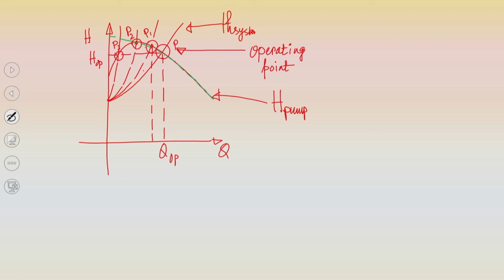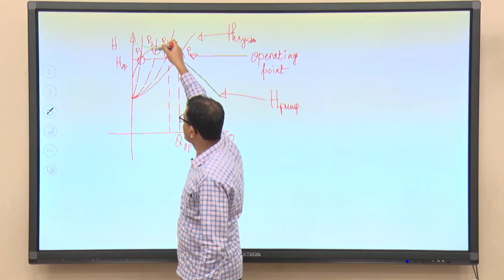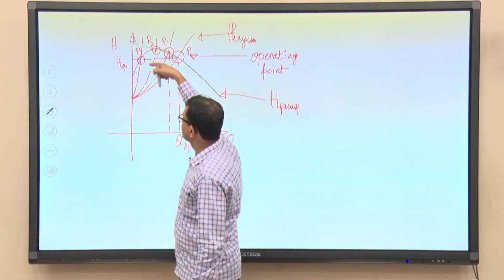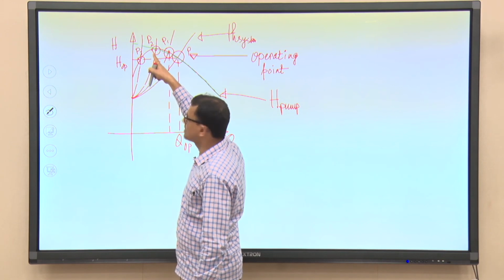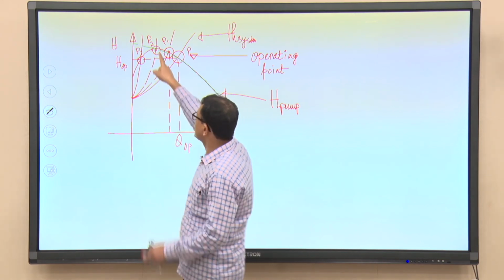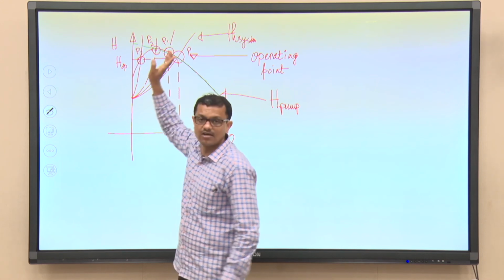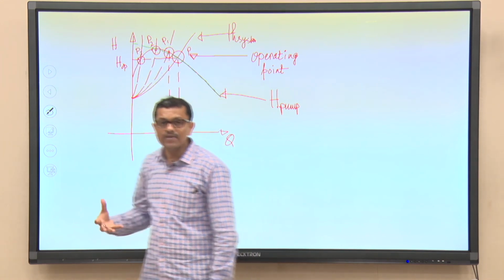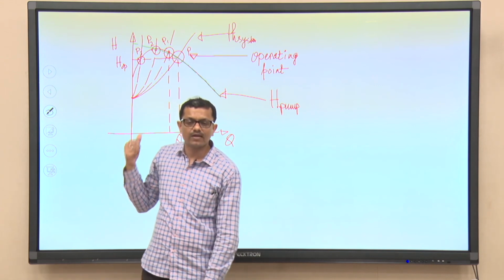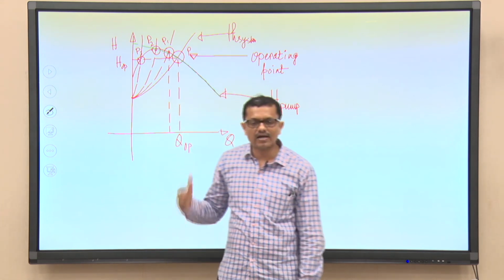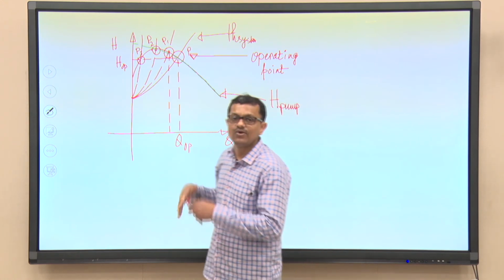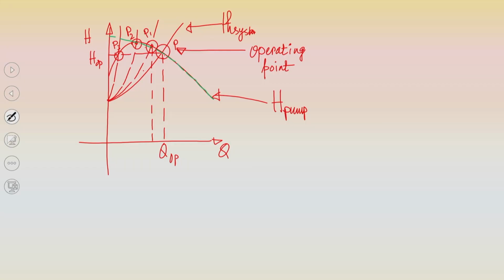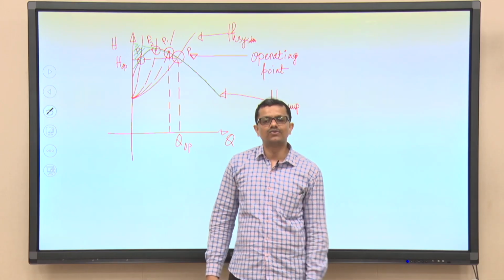Because even though the operator has closed the valve and the operating point is coming to P2, this is not the maximum head, because the maximum head is the shut off head, right. So, the problem associated with this type of trouble, I can say undesirable effect, can be eliminated. If we need to do so, then perhaps it is essential that the separation losses, for which the shut off head is reduced, should be minimized.